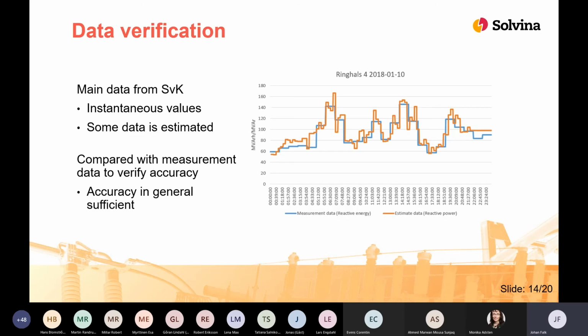So, the data we have used, I want to talk briefly about. For the dates I showed you, data was gathered from Svenska Kraftnät, and this data included voltage levels and active and reactive power flows between the nodes in the area previously shown. This data comes from a program which uses measurement data where there is measurement data. And if measurement data for one data point isn't available, the program uses some kind of estimate algorithm to make estimates for these data points. We do not know which values are estimates and which are measurements. And since there are some estimates, there might be inaccuracies in the data.